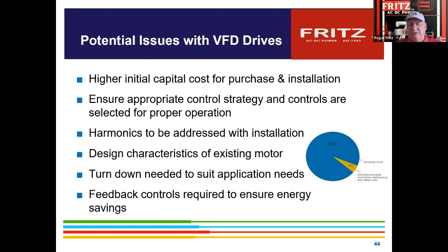There's issues of concern when you get above a large number of drives about harmonics, because we talked about that earlier today in our other meeting. We go into more detail, as you get involved in this, on how to scope and pre-study a facility. It's becoming more and more of an issue across the country. We're working on a project up in Ohio, or I guess Michigan, right now, for a facility where they're getting hit with a $25,000 a month power factor and harmonic penalty, because the building, because of COVID, is not being fully loaded anymore. So the chillers are not running at the optimal point that they were originally designed for. They're all sliding off the curves, but the cost to try to change those chillers out is astronomical.